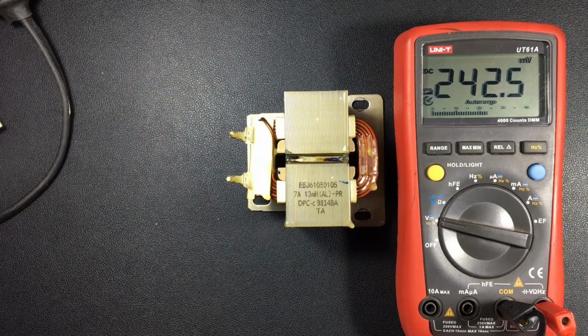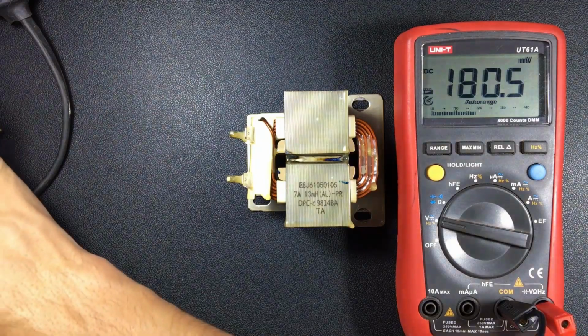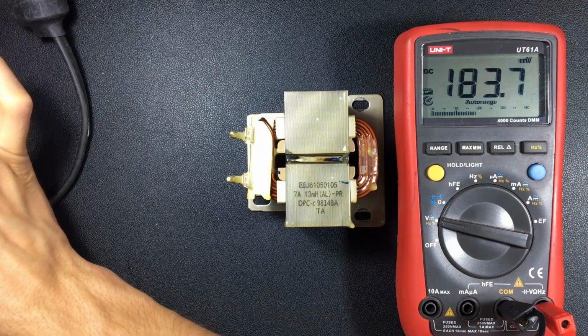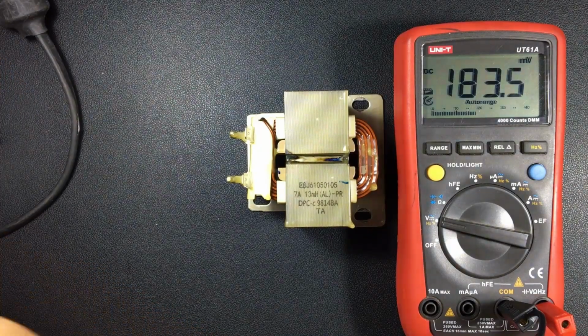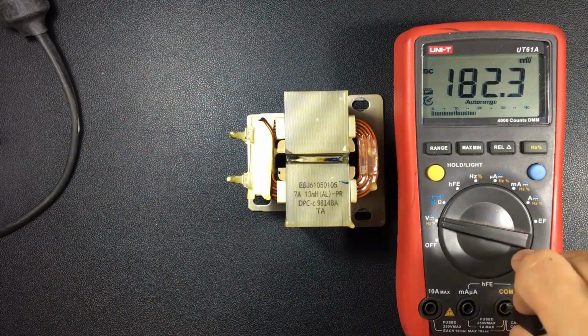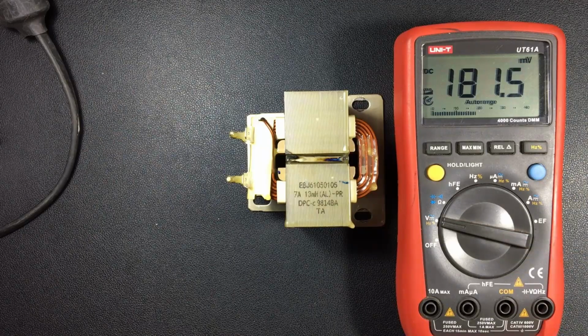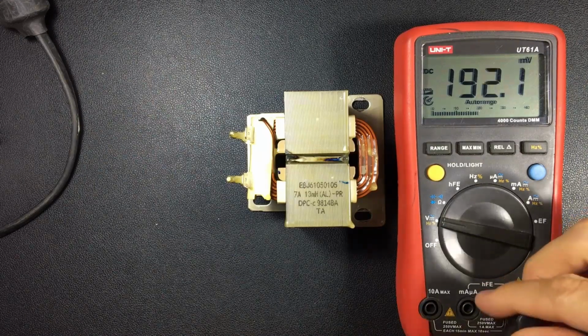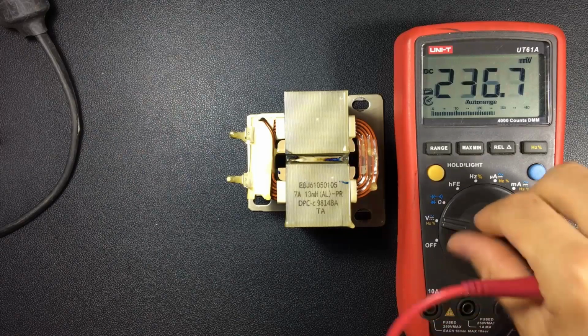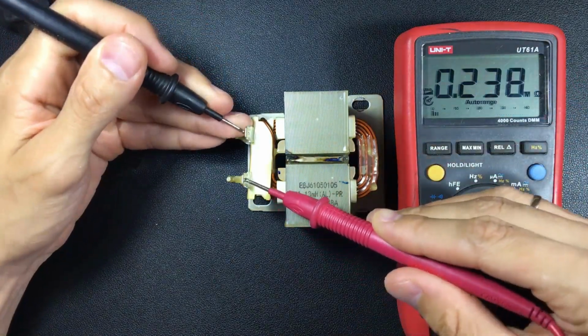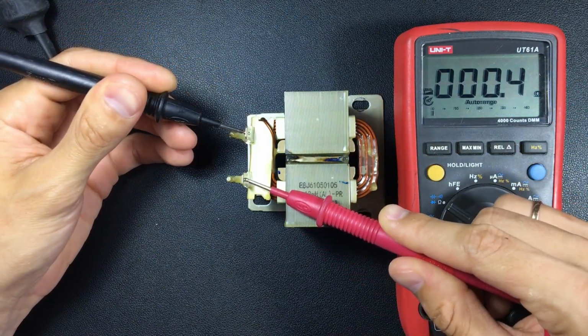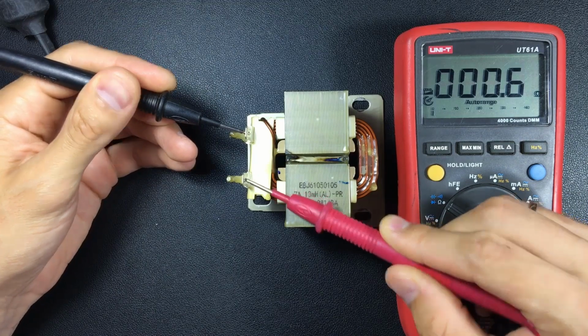If it starts to have resistance, we will have problems in an inverter electronic circuit, and those are the cases in which, for example, we have overcurrent errors. So if you have overcurrent error or even low voltage, check the reactor. If you have a low voltage error, I refer to although the voltage is in good condition, we place the multimeter in resistance and the resistance has to be almost 0.6.